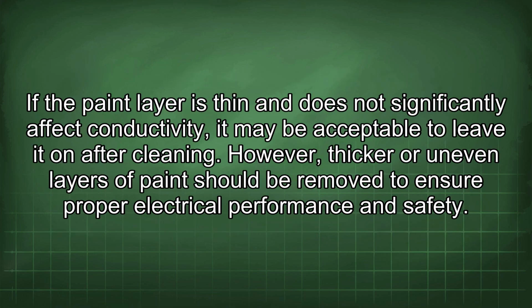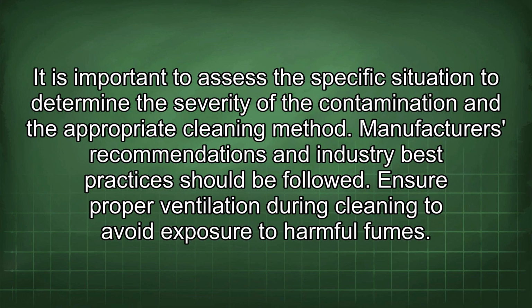If the paint layer is thin and does not significantly affect conductivity, it may be acceptable to leave it on after cleaning. However, thicker or uneven layers of paint should be removed to ensure proper electrical performance and safety. It is important to assess the specific situation to determine the severity of the contamination and the appropriate cleaning method. Manufacturers' recommendations and industry best practices should be followed.